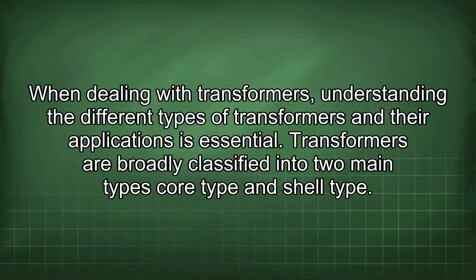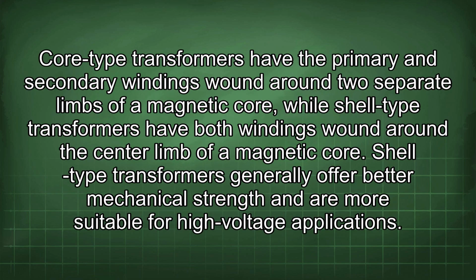When dealing with transformers, understanding the different types of transformers and their applications is essential. Transformers are broadly classified into 2 main types: core type and shell type. Core type transformers have the primary and secondary windings wound around 2 separate limbs of a magnetic core, while shell type transformers have both windings wound around the center limb of a magnetic core. Shell-type transformers generally offer better mechanical strength and are more suitable for high-voltage applications.